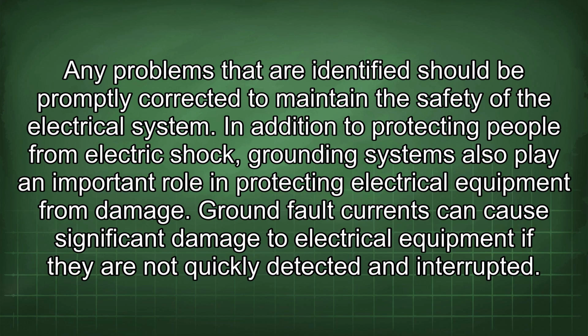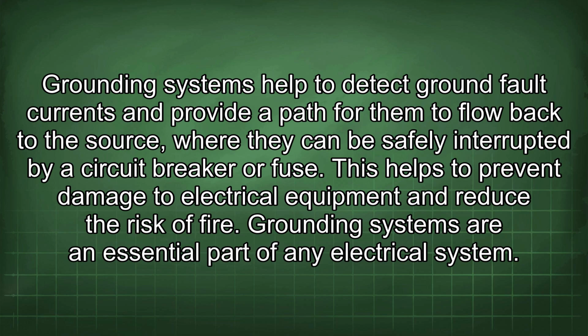In addition to protecting people from electric shock, grounding systems also play an important role in protecting electrical equipment from damage. Ground fault currents can cause significant damage to electrical equipment if they are not quickly detected and interrupted. Grounding systems help to detect ground fault currents and provide a path for them to flow back to the source, where they can be safely interrupted by a circuit breaker or fuse. This helps to prevent damage to electrical equipment and reduce the risk of fire.